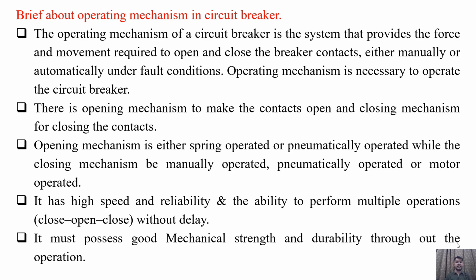Opening mechanism is either spring operated or pneumatically operated, while the closing mechanism may be manually operated, pneumatically operated or motor operated. It has high speed and reliability and the ability to perform multiple operations, that is closing, opening, closing continuously without any delay. It must possess good mechanical strength and durability throughout the operation. So this is the brief information related to operating mechanism of circuit breaker.